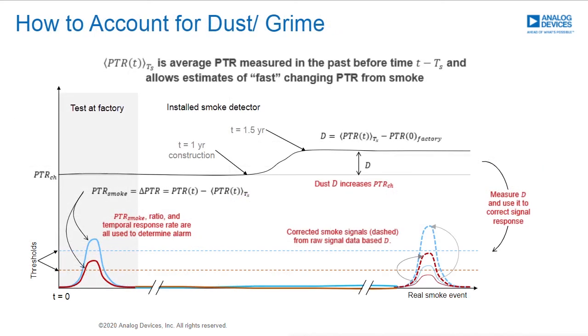This here is a plot that shows how you would account for dust or grime buildup on the chamber. Now, one of the things to keep in mind is that in a standard optical smoke detector, the way that the optics have traditionally been designed, there's no background response. All right, so unless smoke is present, which normally it's not, there's really no way to know that your optics are working.